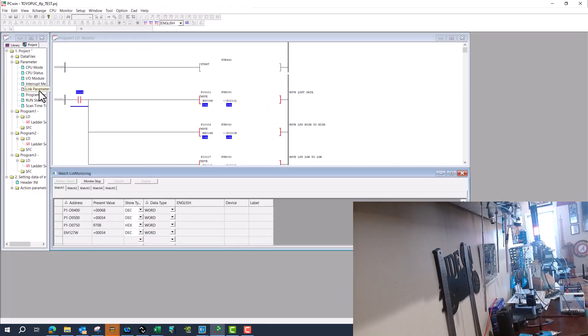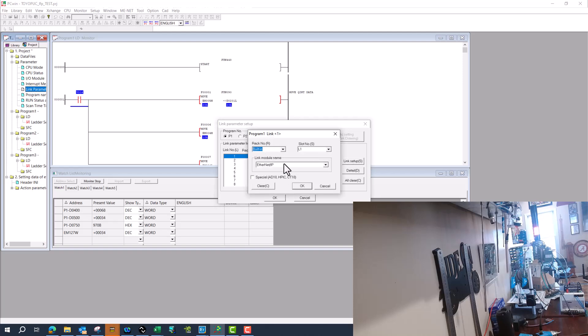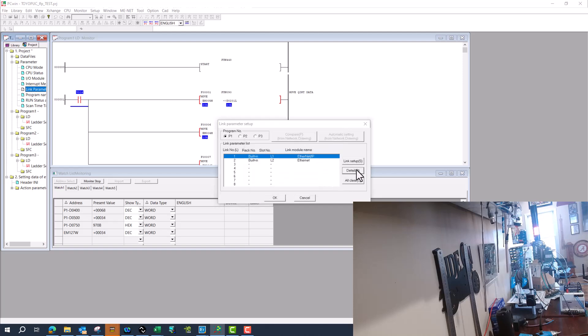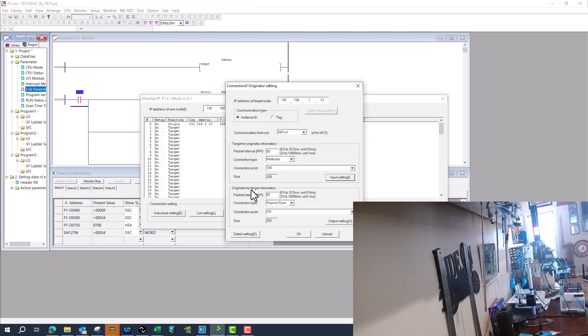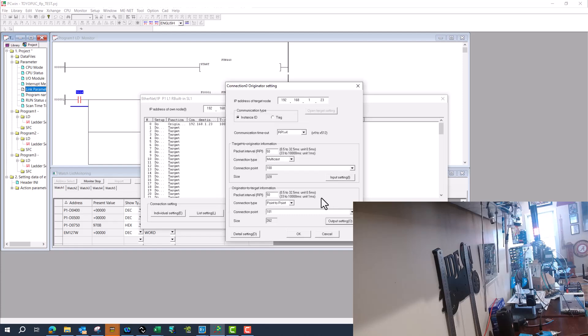So the IP address on that is 192.168.1.23. I've already got it set as a built-in Ethernet port. Now I go to details, and I did change this to do on the originator. Set my IP address, set my instance size, and then told it what byte I wanted to start at, or what address, and how many bytes. So I did that for both originator to target and target to originator. And you see it's the same thing, 262, starting at EM100. So that's kind of the range where the data comes in. If that doesn't match, it will not communicate.